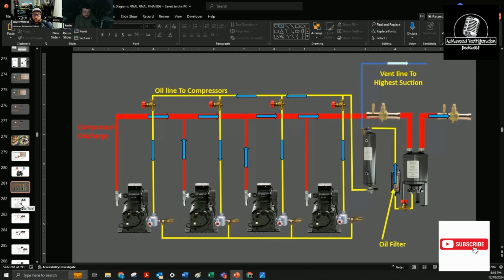And I agree with you. The only problem is if you don't have certain things set up within the program. I've seen systems where, let's say this compressor is the one pulling back the suction, and it happens to be one of those older green compressors that are not Copelands. If it fills up with oil anywhere past the level it should, a lot of times it will grenade. And so that's the point of the oil equalization line.